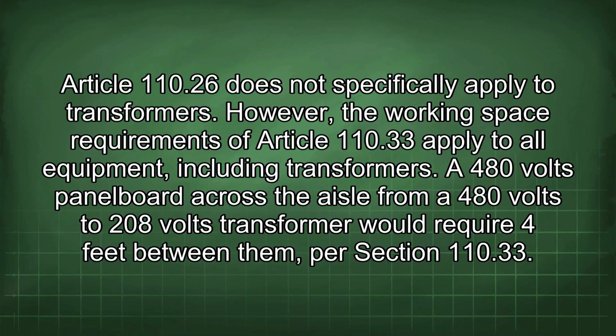Article 110.26 does not specifically apply to transformers. However, the working space requirements of Article 110.33 apply to all equipment, including transformers. A 480 volts panel board across the aisle from a 480 volts to 208 volts transformer would require 4 feet between them per section 110.33.